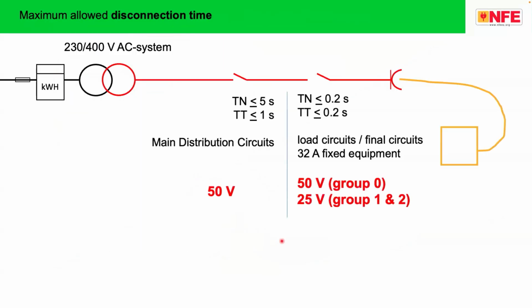One important safety measure which has to be implemented in every hospital is the maximum allowed disconnection time. In a faulty equipment, before the faulty equipment creates a shock or ignites fire, the supply has to be disconnected within a specified time: TN 0.2 seconds, TT 0.2 seconds. There is a small mistake. This is 0.4. But for medical location, group 1 and group 2, the disconnection time is 0.2, means within 200 milliseconds the protective device should work and trip the supply.